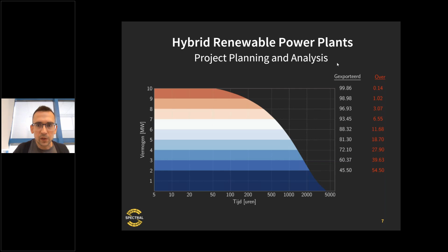The first step is to rate the grid connection based on your renewable plant. Then, if you want to add a large-scale storage installation, you need to reconstruct and simulate the control behavior of that combined power plant. So what we often do is build the optimization algorithms in advance to replicate some of the control functionalities, production output, and total load profile of the plant.